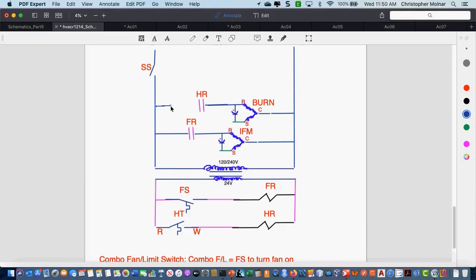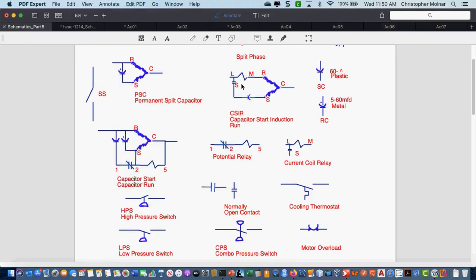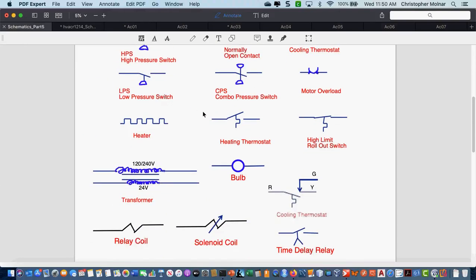Now, a limit switch, is that a cooling thermostat or is that a heating thermostat? Heating. I want it to open on temperature rise, right? Yeah. Open on temperature rise is the one that is a heating. So as it gets colder, it closes. Cooling would be a close on temperature rise. It would close as the temperature goes up.